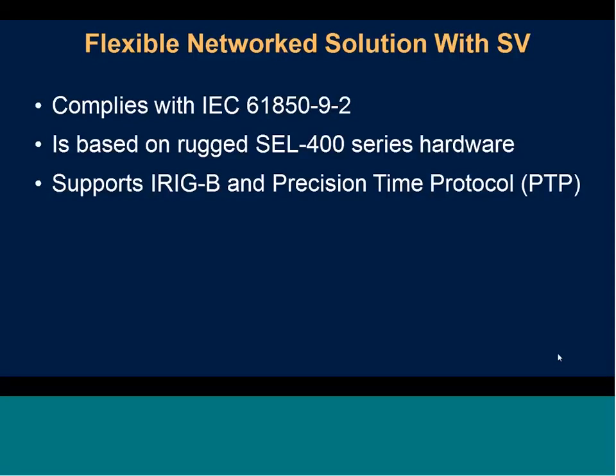The other thing to consider is that because we now have a non-deterministic Ethernet network, we do have to time align all of our data, and so how we do that is by getting time to every unit in the system. With our implementation, we either use an IRIG signal or precision time protocol, which is described in IEEE 1588. It's essentially a way to get high accuracy time through Ethernet connections.